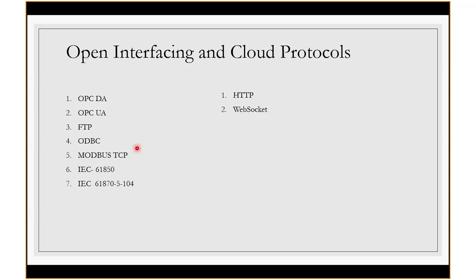This is highly recommended for cloud kind of communication, for real-time data communication, because in OPC standards we always have quality of service - quality of the data - which is very important. Let's assume we are taking data from the SCADA server and we don't know whether it's live data or not. In the OPC protocol itself there's a functionality called quality. If quality is 192, it is good - that's the standard. If it's other than 192, you can ignore that value, because that value may be the previous value, or if the device is restarting, you may get some junk value.